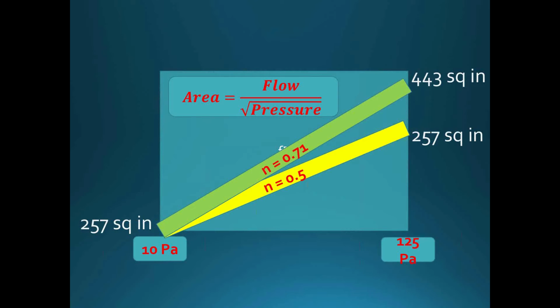So when we use that equation to calculate hold time for inerts, we get a much, much longer hold time. Why? Because the apparent hole, as far as the agent is concerned, is much, much smaller. So the new test procedure that has evolved into NFPA, where we take a test point at 10 and a test point at 50, is able to measure the slope of this curve and take advantage of that fact. The ISO calculations have been using that for well over 10 years, and they've always taken advantage of it. So that's really the reason why.